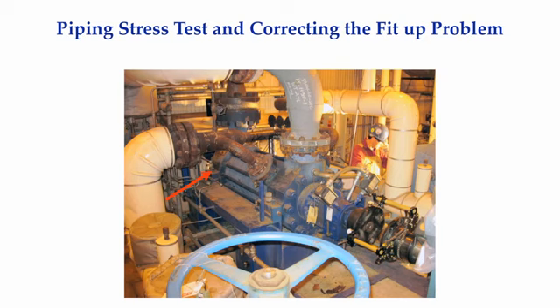We then measured the gap at the discharge flange faces, kept notes, and discussed how we were going to correct this. Since the gaps were not excessive, we decided to alter the alignment correction moves to not only align the shafts, but also fix the piping fit-up problem. This will be discussed further in one of the intermediate alignment tutorials.